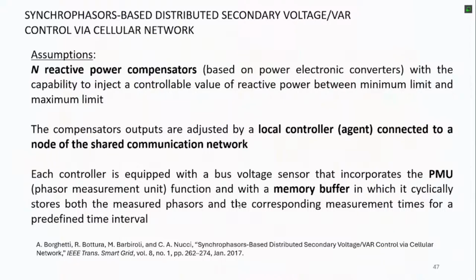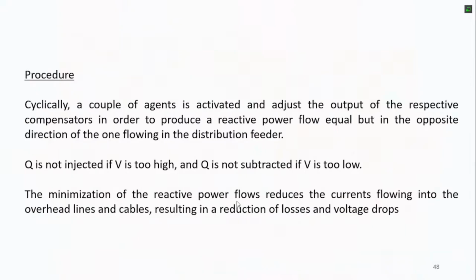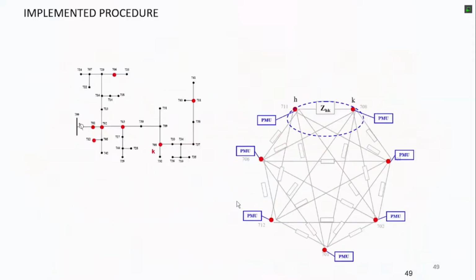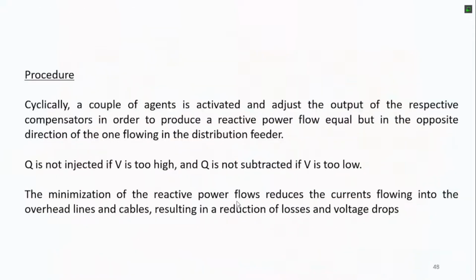At this point, we have the procedure. Cyclically, a couple of agents, so controllers in two photovoltaic units, is activated, and adjusts the output of their respective compensators in order to produce a reactive power flow equal but in the opposite direction of the one flowing in the distribution feeders.